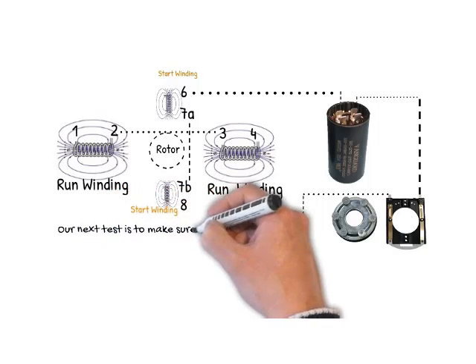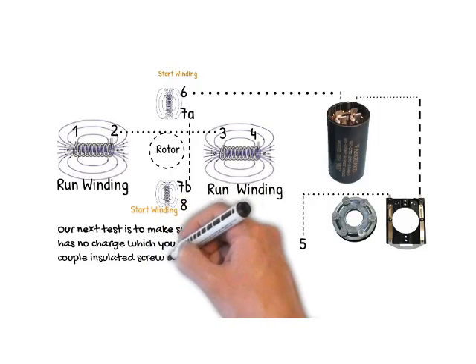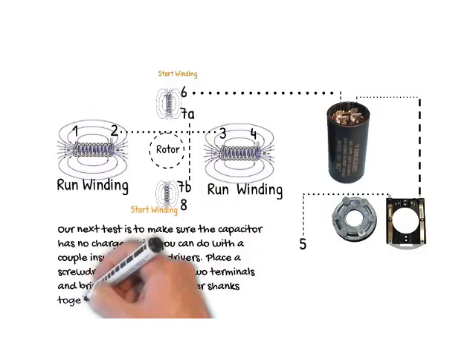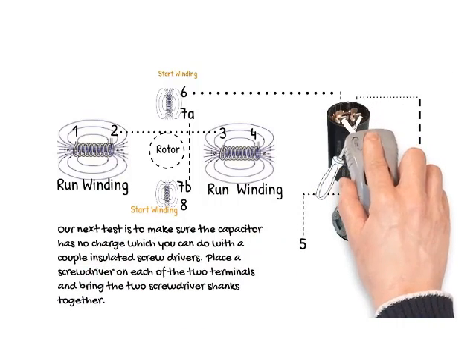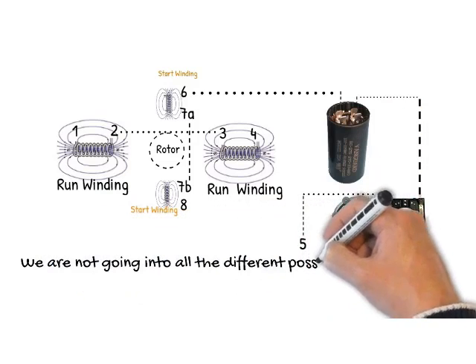Our next step is to make sure that the capacitor has no charge, which we can do with a couple insulated screwdrivers. Place a screwdriver on each of the two terminals, and bring the two screwdriver shanks together. This step will make sure that there is no voltage left in the capacitor.